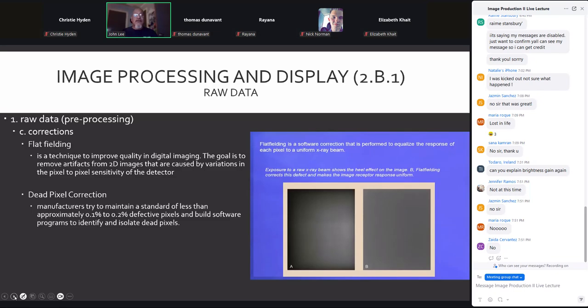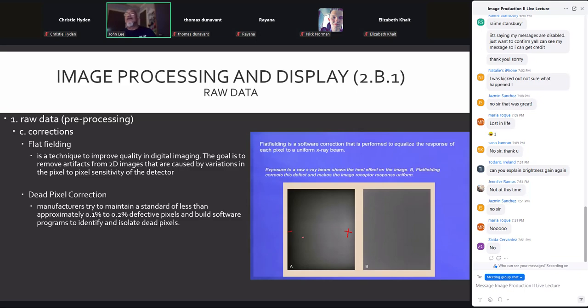Another method of corrections is flat fielding. This is a software correction, and this can equalize the response of each pixel so that we get a uniform display. Really, if we look at this being an example of what we would see with the anode heel effect, where the anode would be at this end, and the cathode would have been at this end, flat fielding would allow for an even tone across the image receptor.